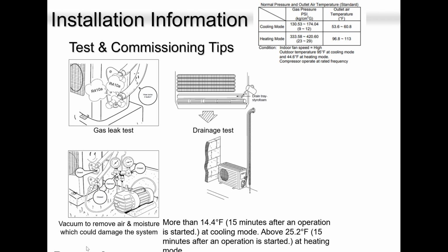Always remember, when you have the time, when the system is under vacuum or under pressure, open up the indoor unit, pour some water. Take a mug or jug, fill with water, pour in the drain pan. Make sure it's flowing nicely outside, because maybe you are doing your job in winter time or fall time. So the homeowner is not going to put the unit in cooling, and maybe there is not enough humidity. So test it manually. How do you test it manually? Pour enough water in the drain pan, make sure everything is going out. These are simple things. You don't have to rush.